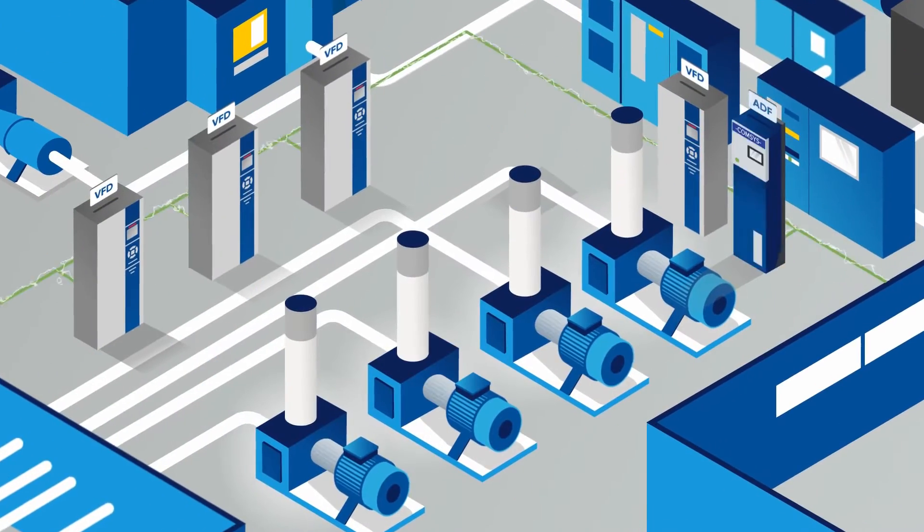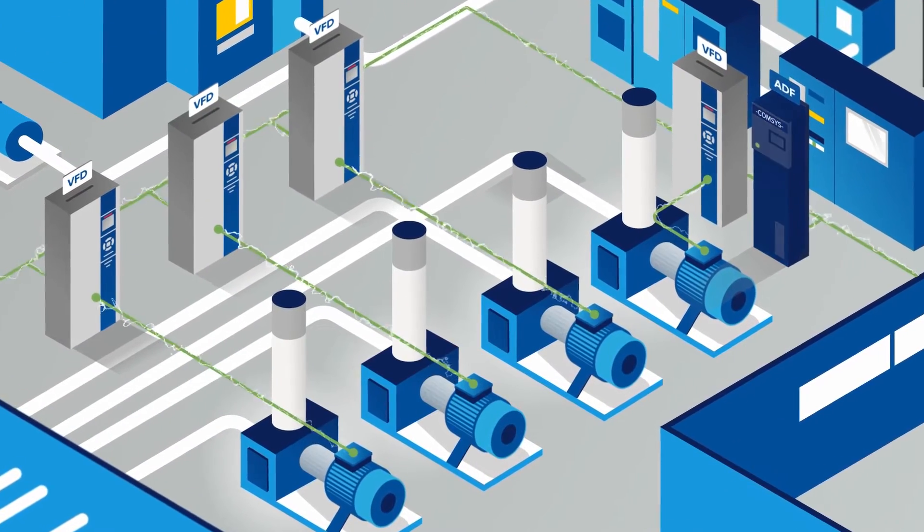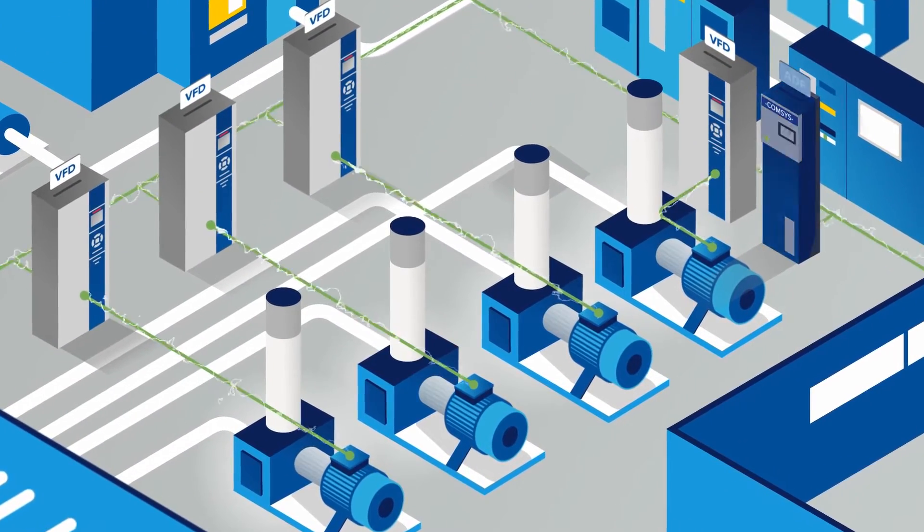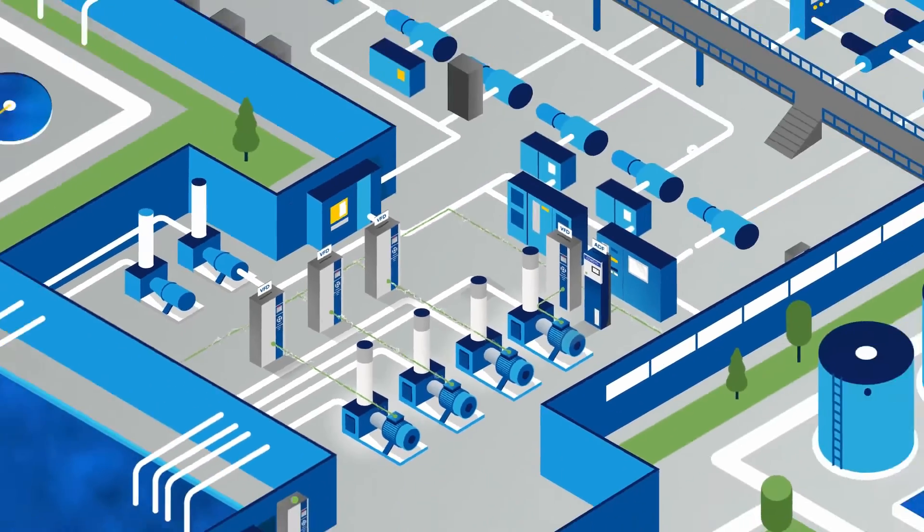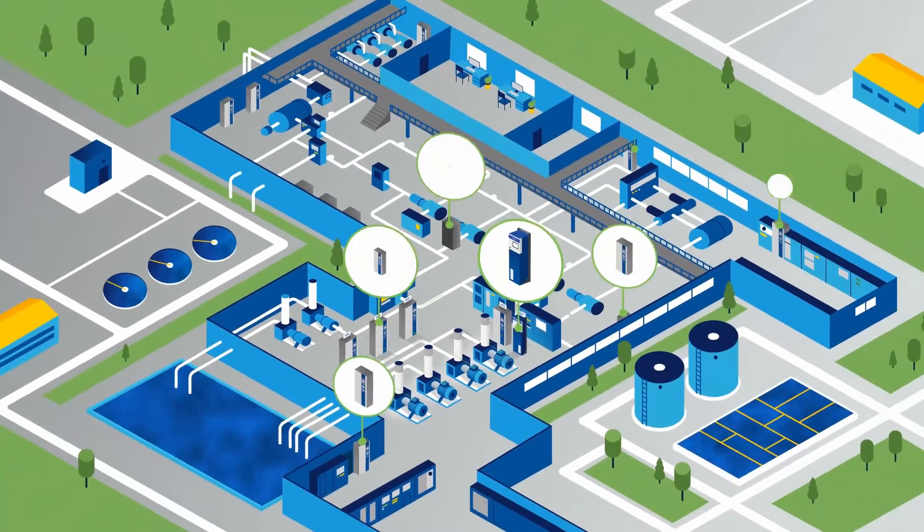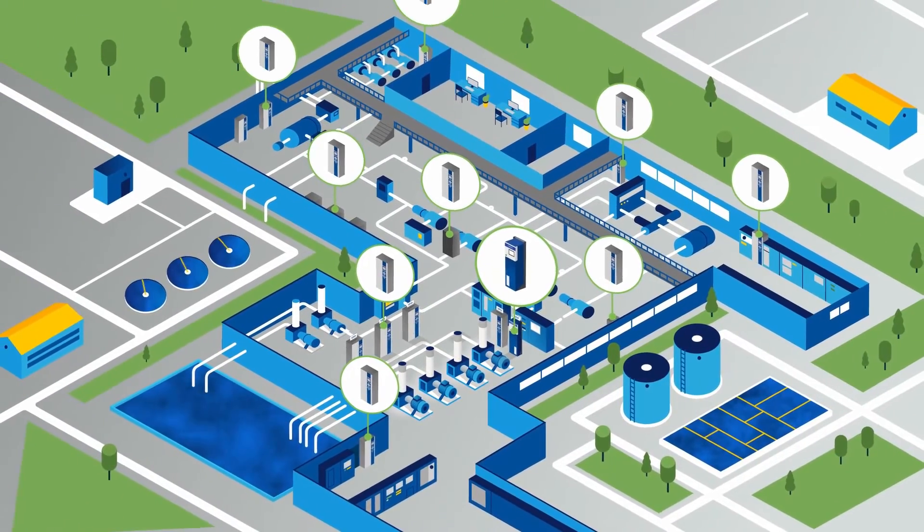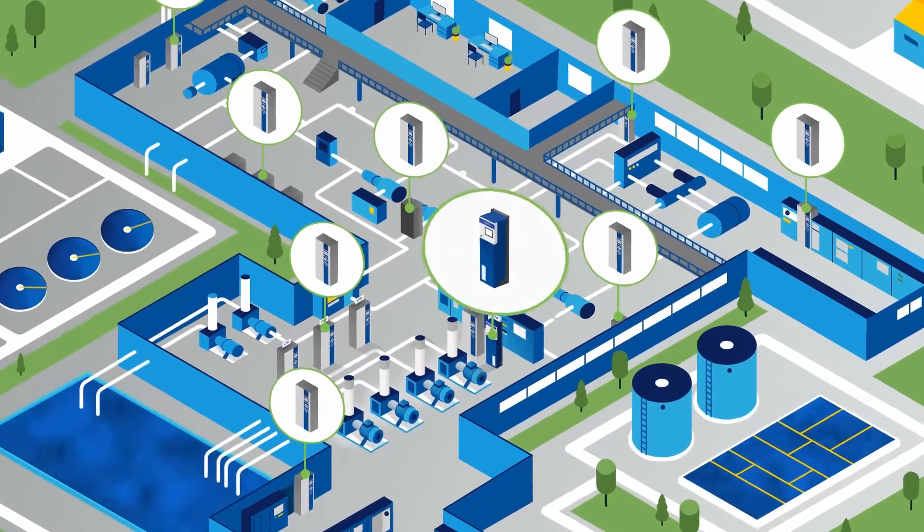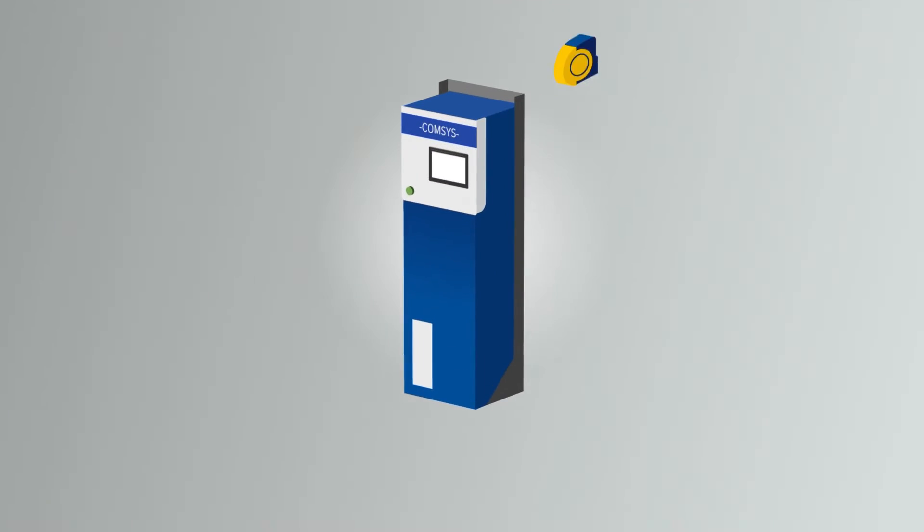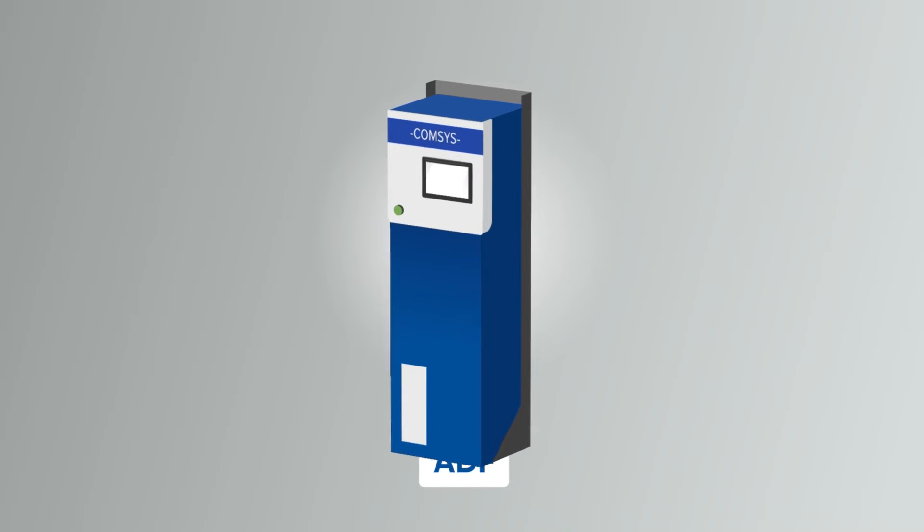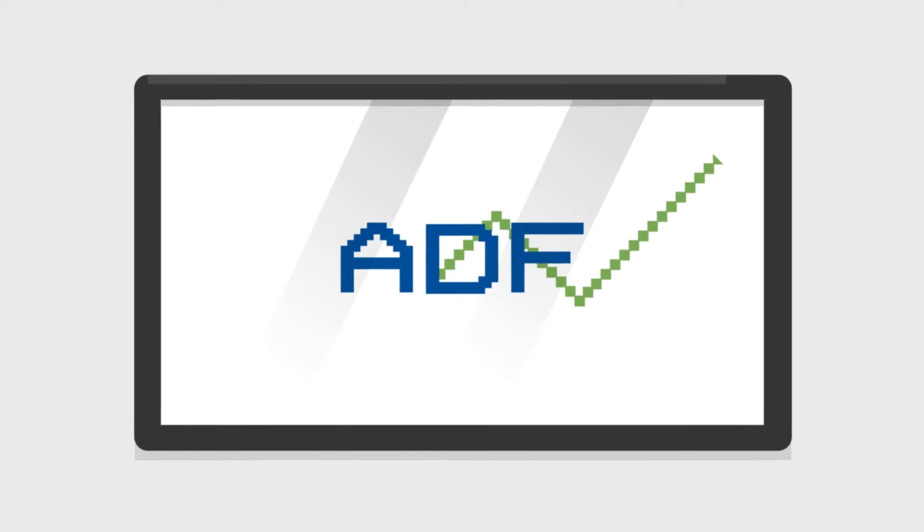An ADF, however, is always connected in parallel to the loads and sized to your specific need, making it a smaller, more efficient solution and resulting in higher redundancy. Thanks to ADF being smaller in size, it also results in lower losses, thus making it the sustainable choice.